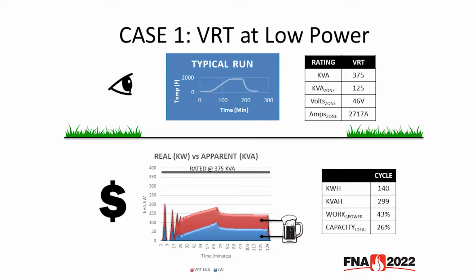The red area represents kVA, and the blue area represents kW. The reference here on the right is the beer mug analogy of the power triangle. The blue area, kW, is real power, or the power that's doing work in the furnace. The red area, kVA, incorporates the wasted power, or the foam on top of the beer, which no one wants. This electrical trend is what we expect to see. As the furnace is ramping up in temperature, it takes more energy at higher rates as the furnace is heating up. Then, when the furnace reaches the soak phase, the energy requirement drops down to a plateau because we're simply maintaining a heat.